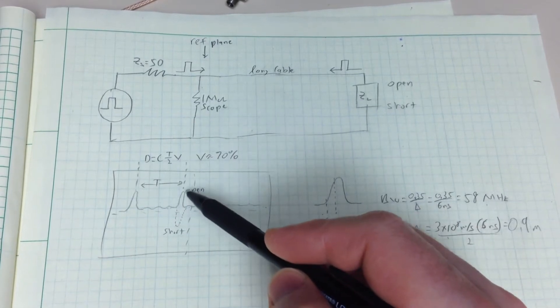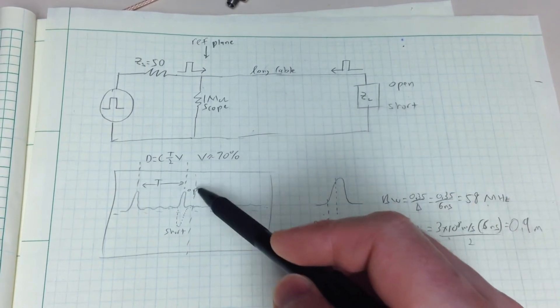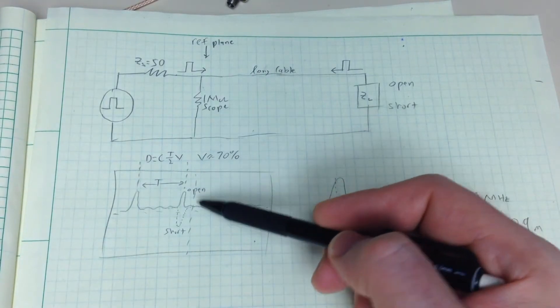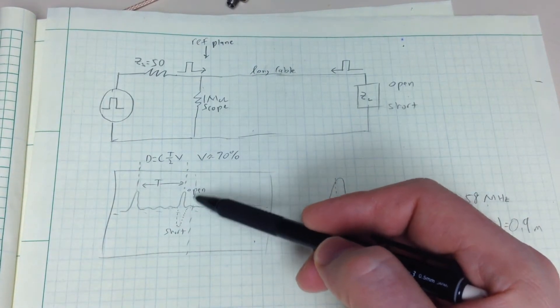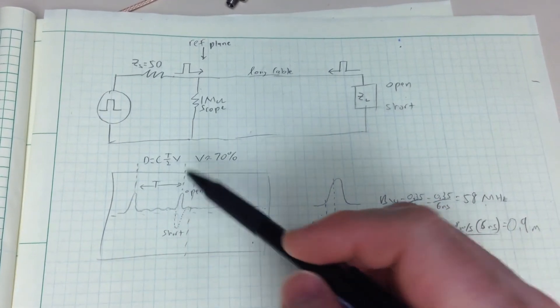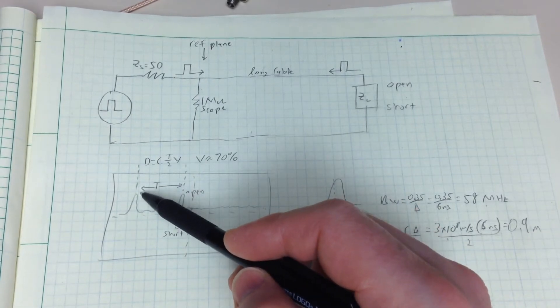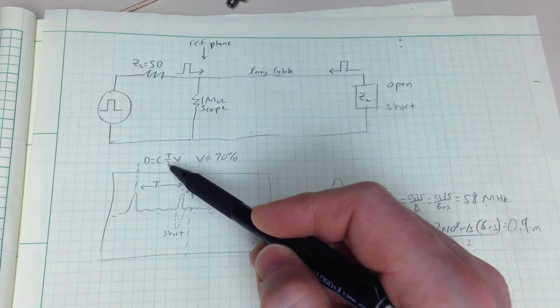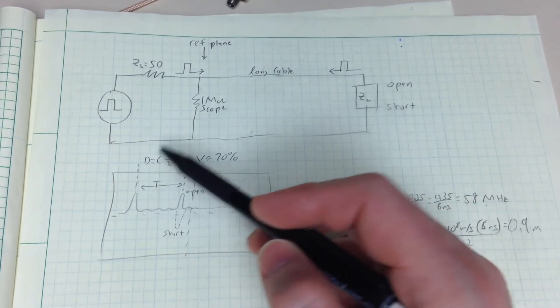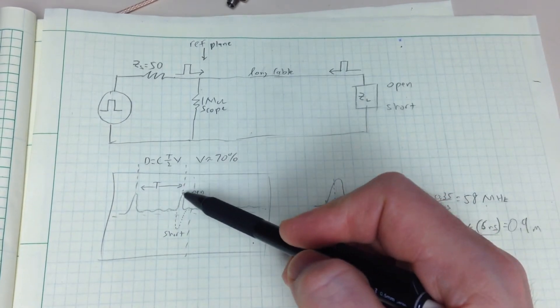And this return pulse can either have a positive amplitude if the discontinuity over here is an open or it's going to have a negative one if it's a short circuit. If you measure the time between the first pulse and the second pulse and you divide that by two since it's a two-way trip down the cable and back, multiply that by the speed of light, you can find the distance from the beginning of the cable to where the reflection occurred.